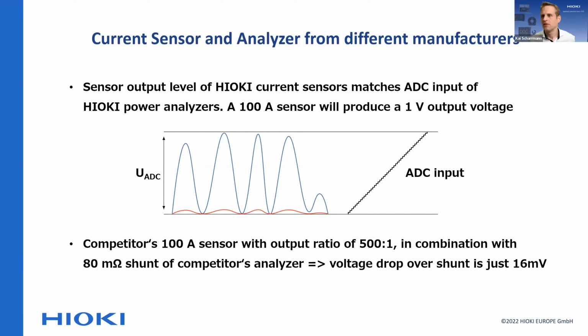That's typically the kind of difference between a matching system and an unmatched system. I actually looked at a competitor setup - a competing brand of power analyzer combined with a different brand making the current sensor. This combination isn't common, but you definitely see it in the market. If you compare a 100 amp sensor with an output ratio of 500 to 1, combined with an 80 milliohm shunt on the competitor's analyzer, the voltage drop over the shunt is only 16 millivolts.